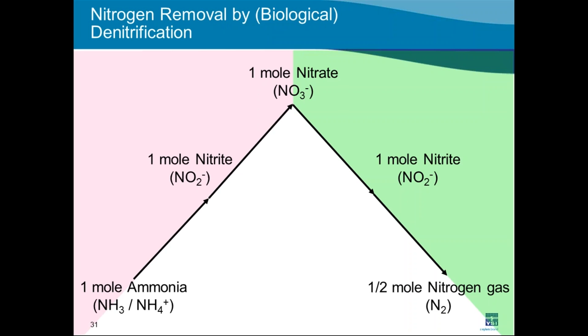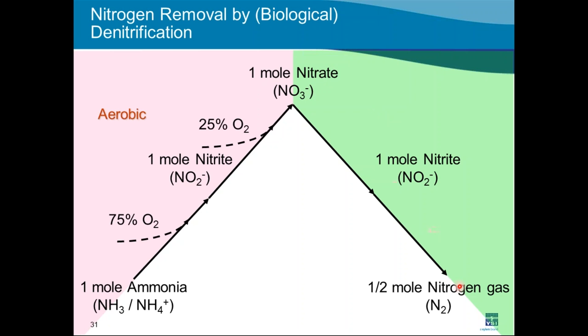The last application featured is nitrogen removal by biological denitrification. Ammonia entering the plant is converted to nitrate under aerobic conditions (nitrification). Under a different set of conditions — anoxic, with very low DO — that nitrate can be converted to nitrogen gas, which bubbles out of the system, removing nitrogen. Sufficient carbon is needed to drive the denitrification reaction.